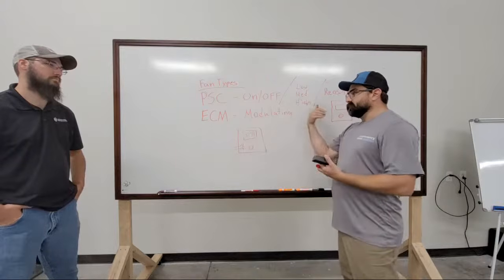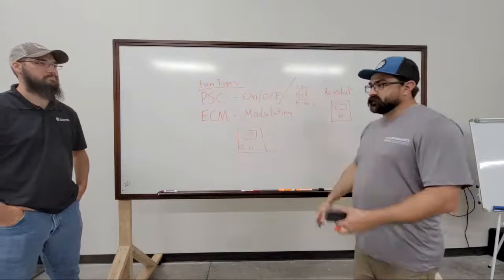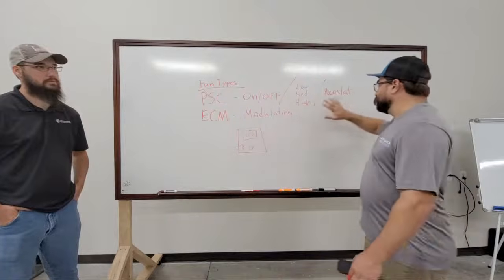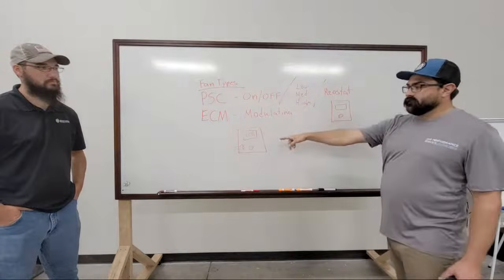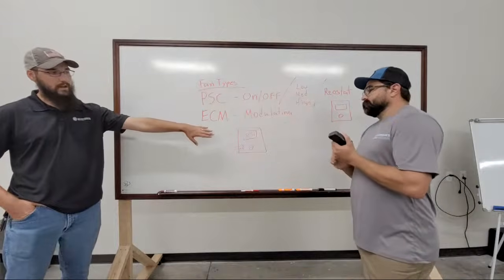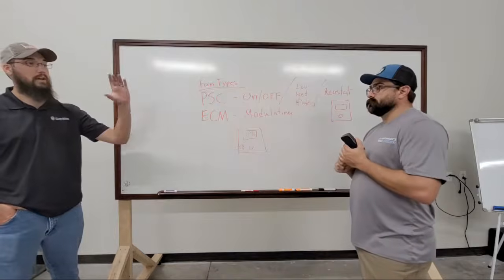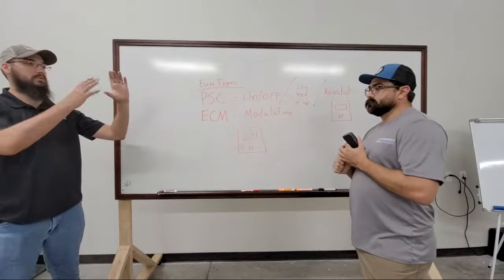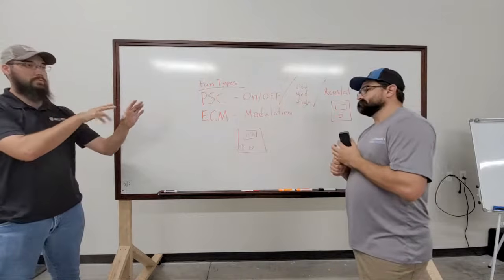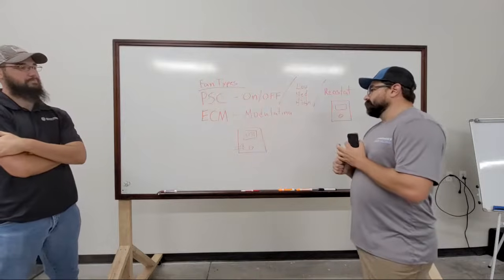Usually you'll open up your compartment and it's a green board inside with a bunch of wires coming to it with a Molex plug or something of that sort. If they're external, they're acting more like a rheostat. Well, in the Titus ones I've seen, this was not much more than an interface. And so it had the regular control module inside, and then that was just interfacing to it. It still had all the normal terminals and everything. Yeah, inside the box, but external, okay.